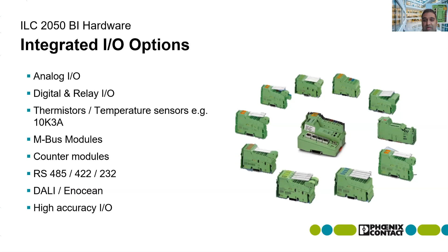These are just some of the typical integrated I/O options. We do analog inputs, outputs, digital, and relay, temperature sensors, MBus for energy metering as I said earlier, further Modbus modules, so RS-485, and DALI for the lighting. So you can see the flexibility of the hardware is quite important, because with other vendors there might be a particular protocol that you want to talk to or a particular requirement that you might have, and the module that the vendor has might not support it. So it's about being able to look at the flexibility of all of these modules that we provide.